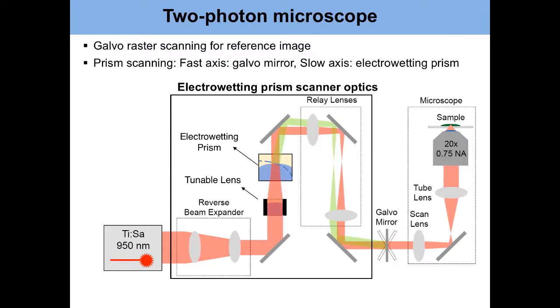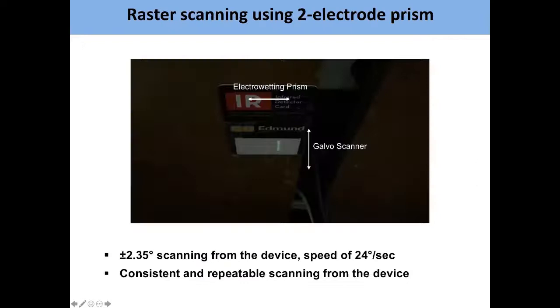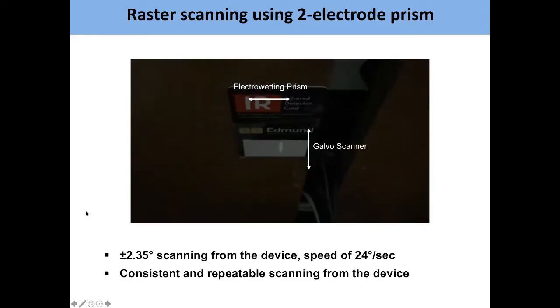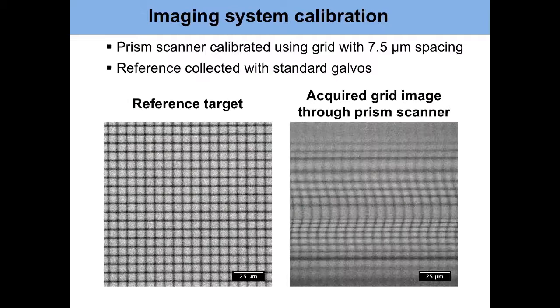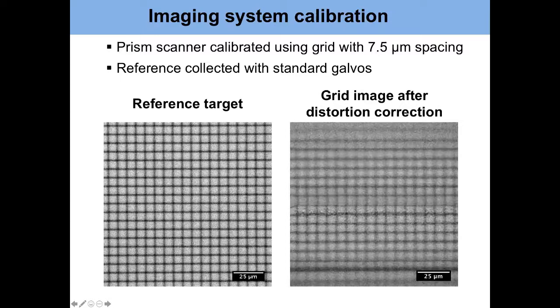So in our lab, in our custom-built laser scanning microscope, we effectively added an additional relay where we imaged the electrowetting prism onto the galvo mirrors. And then we could actuate just one axis of the galvo mirror and use the electrowetting prism to scan the other axis. So the galvo was providing the fast axis, and the electrowetting prism was providing the slow axis. Okay, and the electrowetting prism doesn't give you a smoothly changing scan angle with voltage. So on the right, you actually see this distortion, but with computation, you could correct for that.